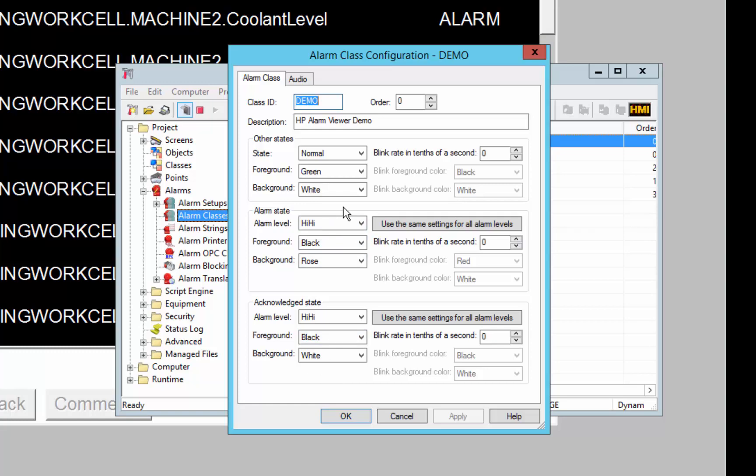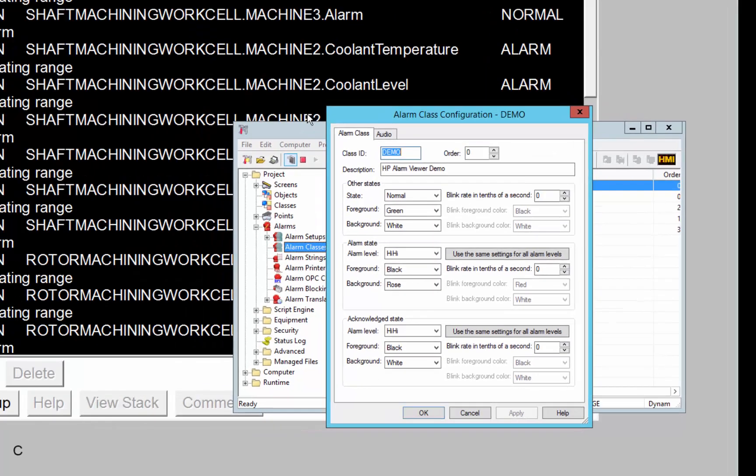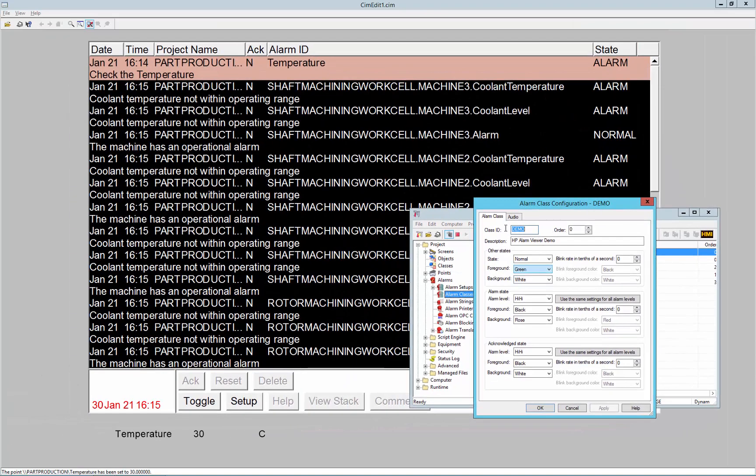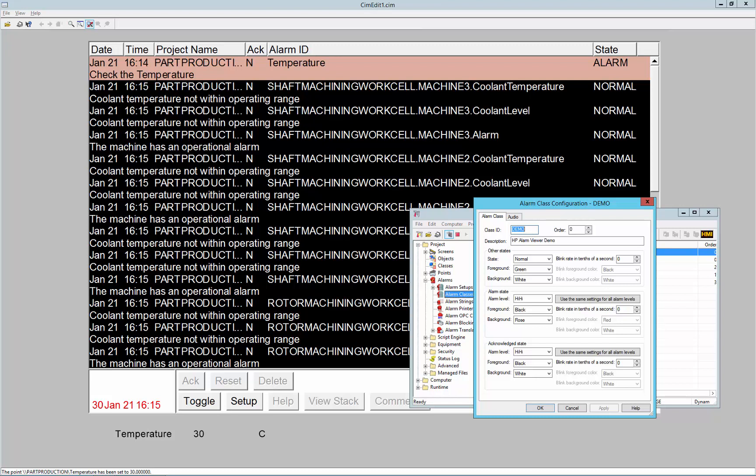So I'll just show you, so you can see that when I applied this demo state to the temperature, it immediately shifted the alarm appearance because I'm in dynamic mode in CIMPLICITY. So that alarm class change took effect immediately, and because it is in alarm, you can see that its foreground is black and its background color is rose.